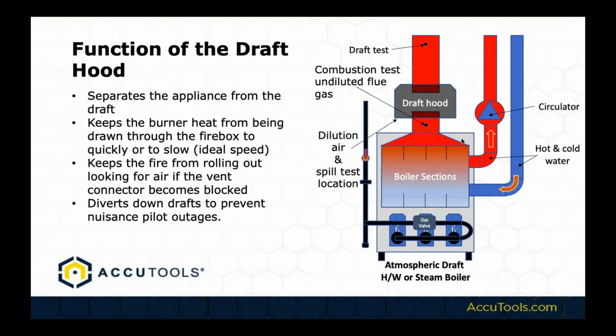Now, typically when we measure draft, what we're talking about is a draft hood. And a draft hood is really, really cool. It's sort of a lost technology, and you don't think about it much anymore. People go, oh, well, the draft hood's obsolete, we don't see them. But you walk down and look at any hot water tank in a basement, and 99% of them have draft hoods on them. We still see a ton of them in the industry, and there's still a lot of older appliances out there that have draft hoods. So they're really worth talking about.